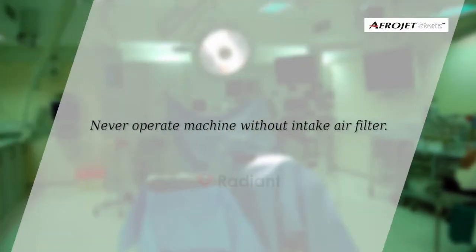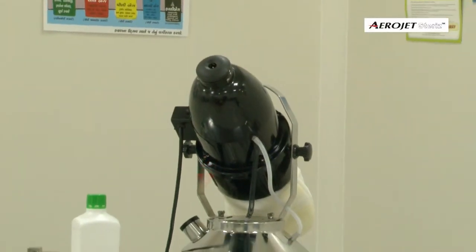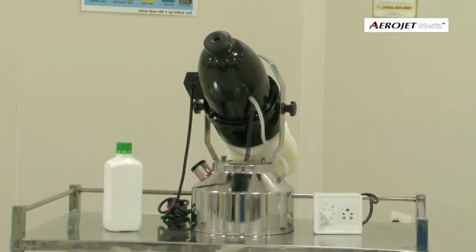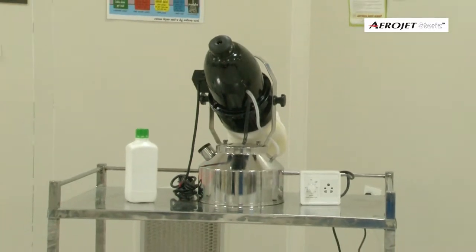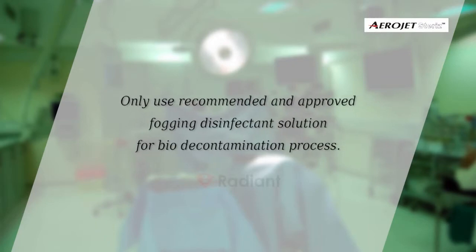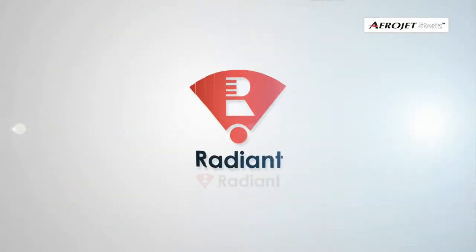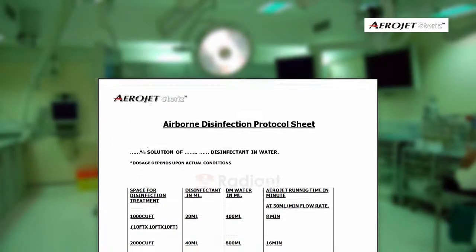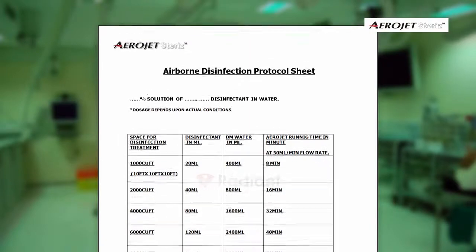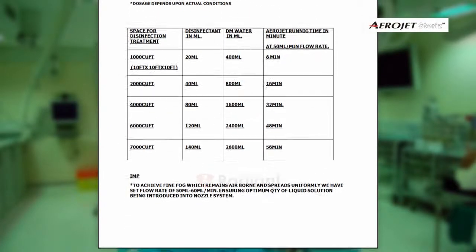High speed motors of the machine should not be kept running continuously for more than one hour. Never operate the machine without the intake air filter. Our machines can be used with many leading environmental disinfectant formulations and brands. Only use recommended and approved fogging disinfectant solution for the bio decontamination process. Contact Radiant Enterprise for better understanding and guidance.